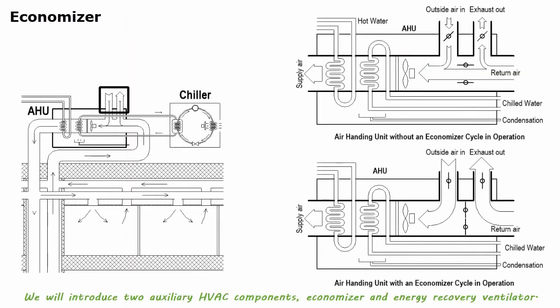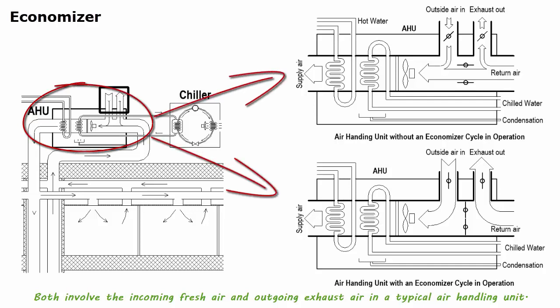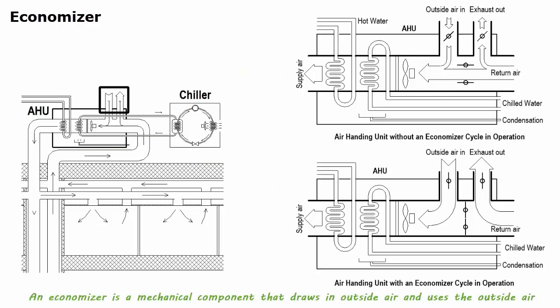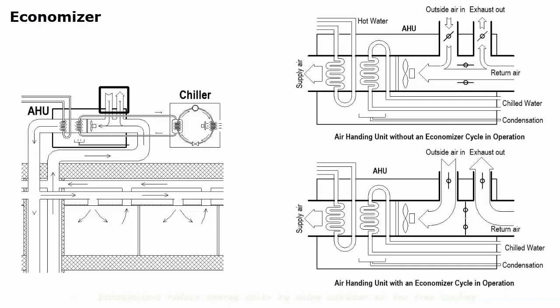Next, we will introduce two auxiliary HVAC components, economizer and energy recovery ventilator. Both involve the incoming fresh air and outgoing exhaust air in a typical air handling unit. An economizer is a mechanical component that draws in outside air and uses the outside air only for cooling a building when the air temperature is cool and dry enough, and this is called free cooling. The entire or a substantial part of the return air from the space is released to the outside.